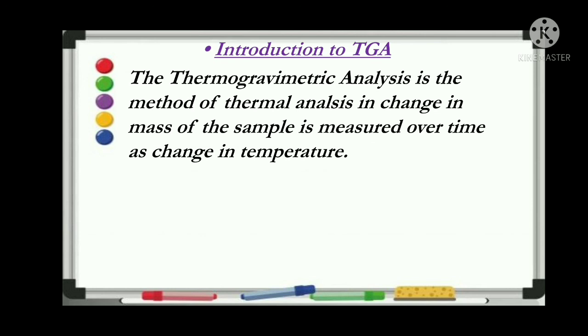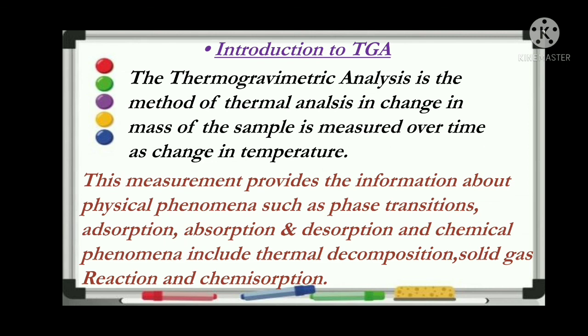After measuring the change in weight of the sample, what can we observe from this method? The basic principle is that we can study physical phenomena as well as chemical phenomena. In physical phenomena, we observe phase transition, adsorption, and desorption. From the chemical phenomena point of view, we can study thermal decomposition — at what temperature the decomposition of the sample takes place — solid-gas reactions, and chemisorption.